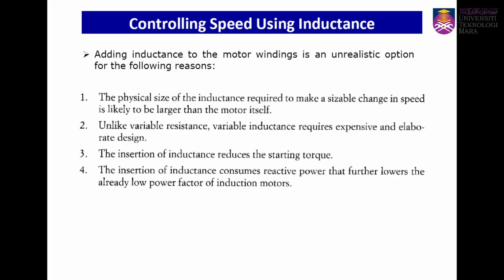Unlike variable resistance, variable inductance requires an expensive and elaborate design. You have to really look into how you are going to design the inductor. When you design it, you have to consider the current, the winding, the flux, and the saturation of the inductor. Number three, the insertion of inductance reduces the starting torque. So you may gain some advantage, but then you have a problem with the starting torque. The insertion of inductance also consumes reactive power that further lowers the already low power factor.